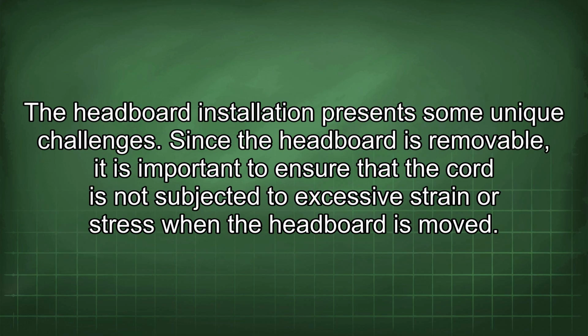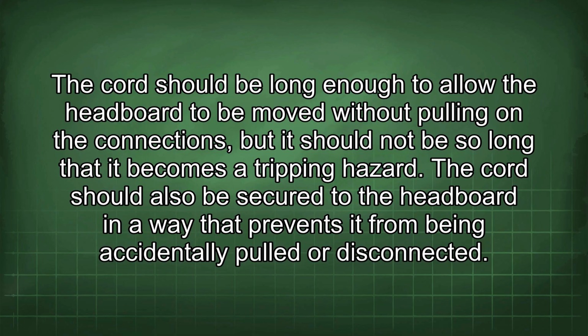The headboard installation presents some unique challenges. Since the headboard is removable, it is important to ensure that the cord is not subjected to excessive strain or stress when the headboard is moved. The cord should be long enough to allow the headboard to be moved without pulling on the connections, but it should not be so long that it becomes a tripping hazard.